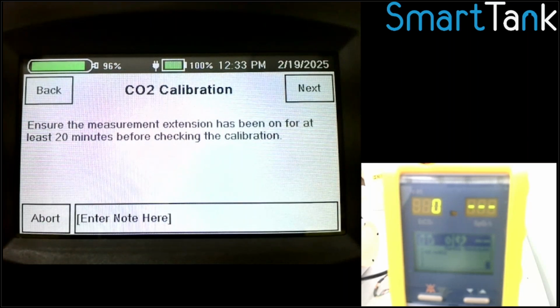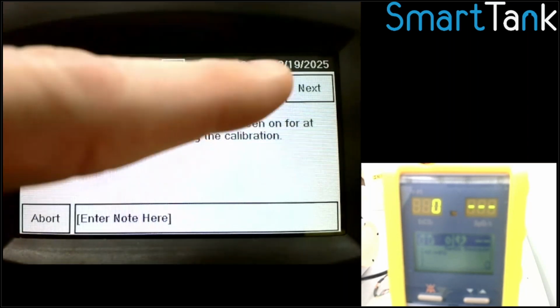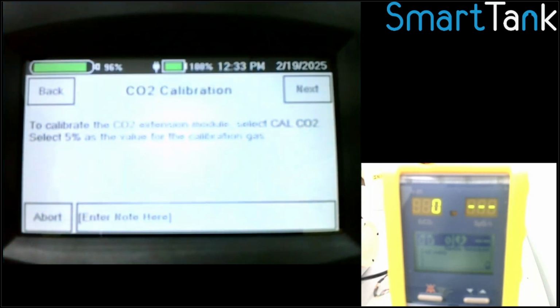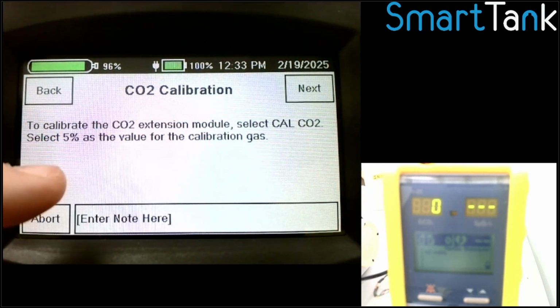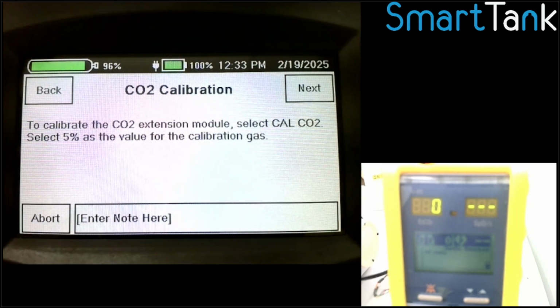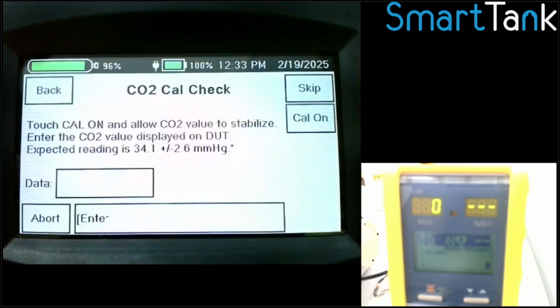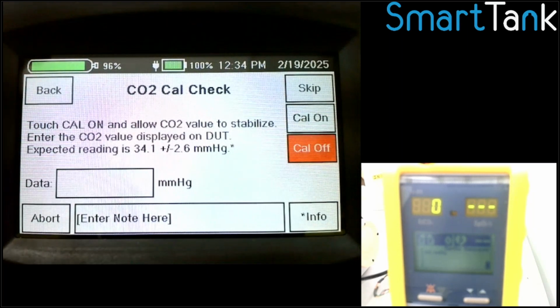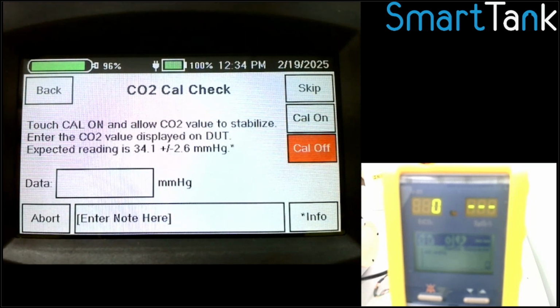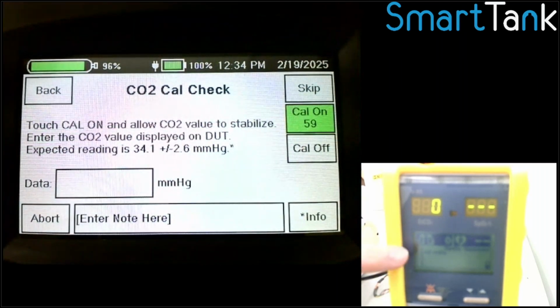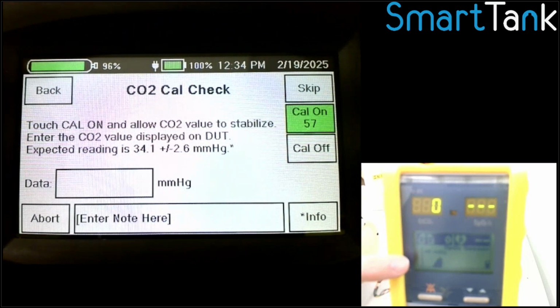And now we get to the last thing, which is the CO2 calibration. Again, it's suggesting 20 minutes. I'm not going to calibrate, so we'll simulate this. It's telling you to go to a certain module and to get to a certain screen. And then at this point, it's saying, hey, when instructed to turn on the CO2 or deliver gas, go ahead and touch cal on. So I'm going to do that. If you watch the yellow device over here, you'll see it actually come up on the graph where it's actually getting CO2 gas now.